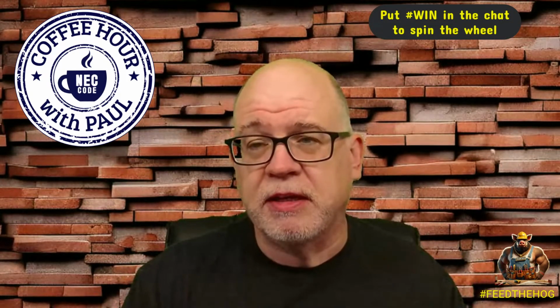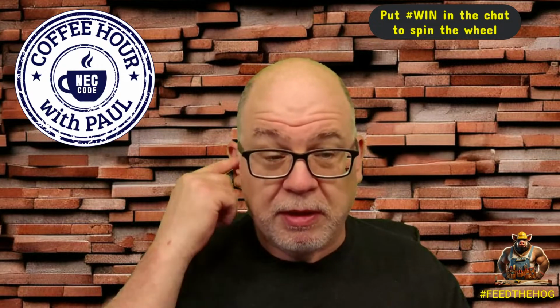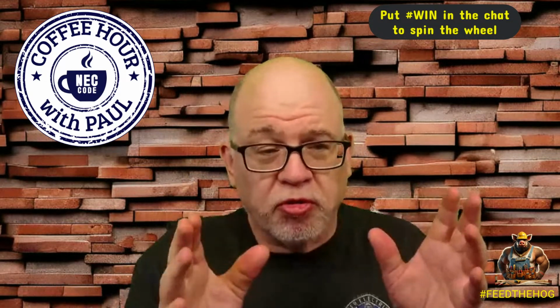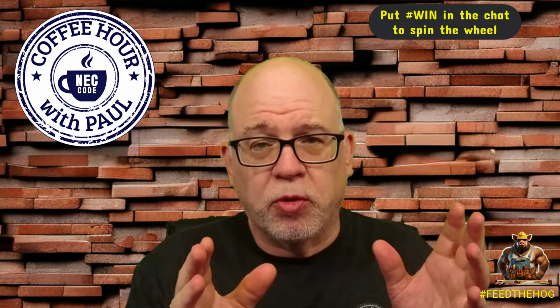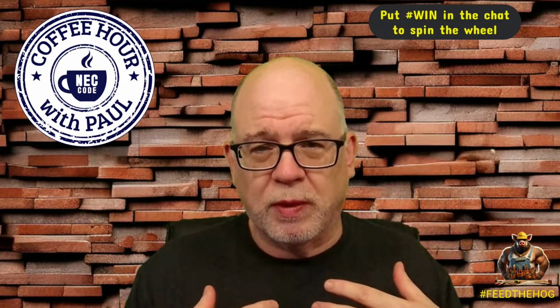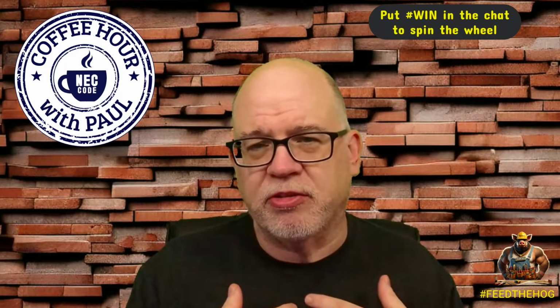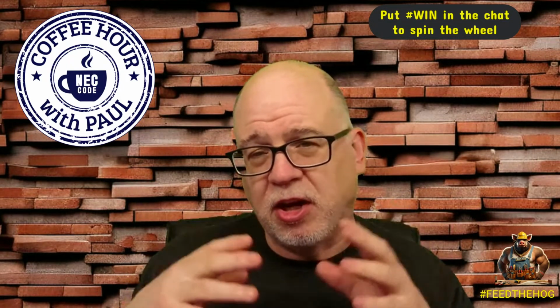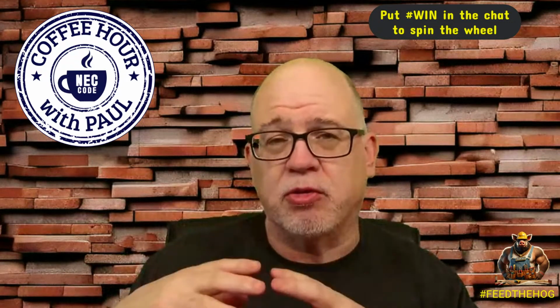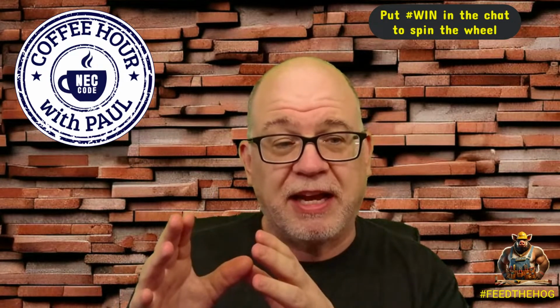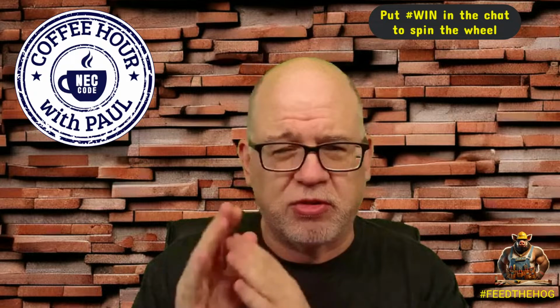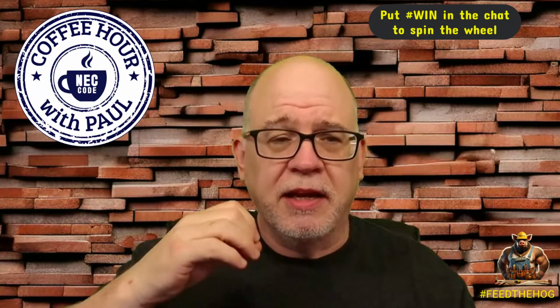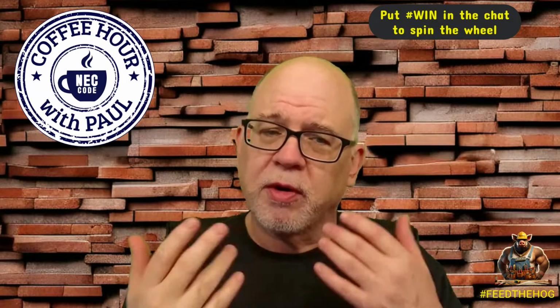But there was no other rule in there that's going to give you a break when it comes to the lighting. And the other issue is you're never going to have the multifamily where the commercial part of the building is going to do anything within your individual dwelling unit. That would be a violation in the National Electrical Code, because your individual dwelling unit can only supply loads that are in your individual dwelling unit, right? Not outside that dwelling unit. So I think it's like 210.25 or something. So important to understand that we don't want to mingle the two.